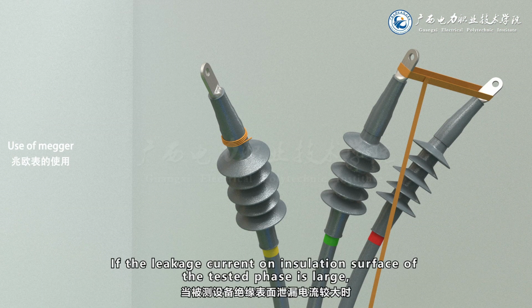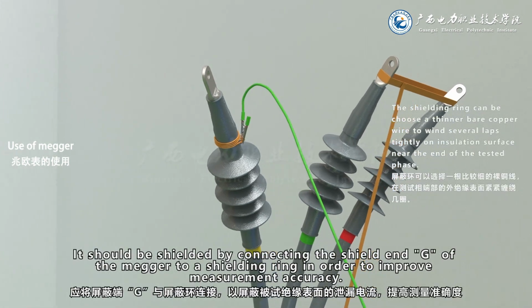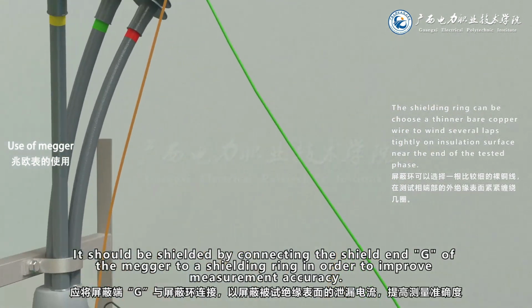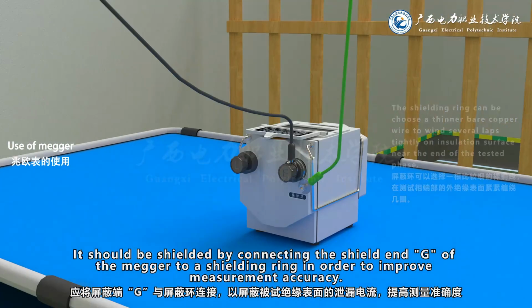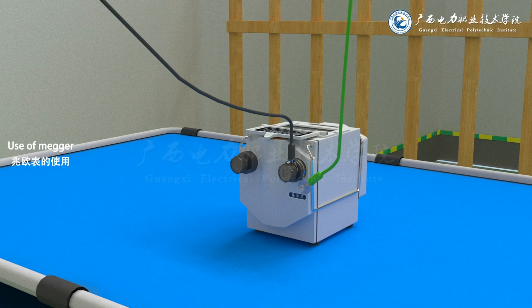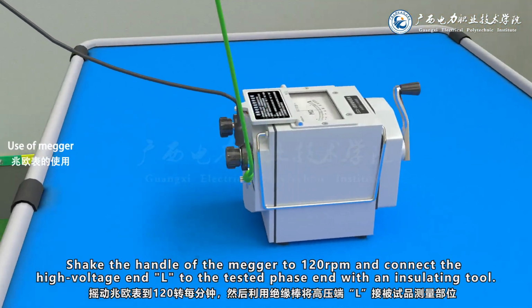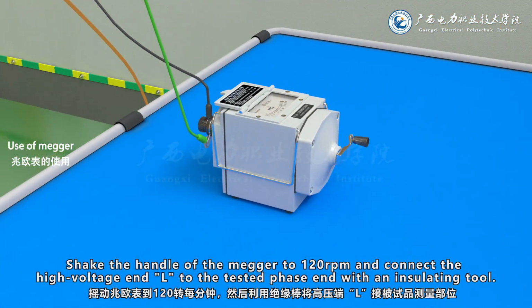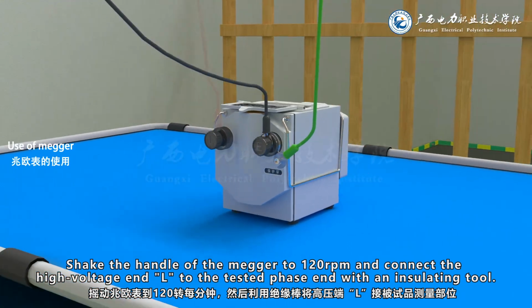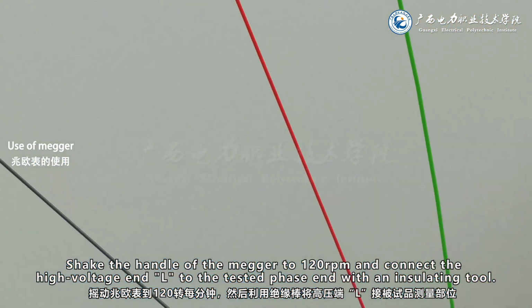If the leakage current on the insulation surface of the tested phase is large, it should be shielded by connecting the shield end G of the Megger to a shielding ring in order to improve measurement accuracy. Shake the handle of the Megger to 120 rounds per minute and connect the high voltage end L to the tested phase end with an insulating tool.